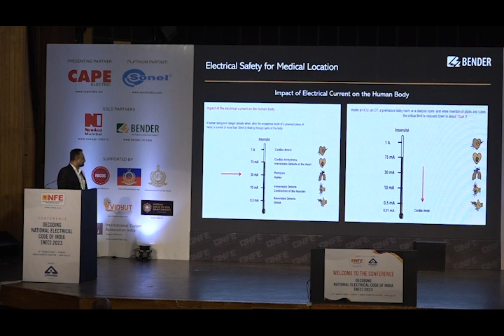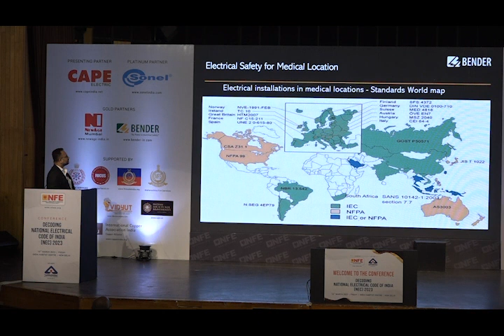This is the basic world map. The green colored countries follow the IEC standard, whereas NFPA standard is followed by American countries, America, Canada, and Australia. Some Gulf countries don't have their own standard, so they follow either NFPA or IEC depending on which country the hospital owner's sponsorship comes from. India is a constituent body of IEC, so here we follow the IEC standard.